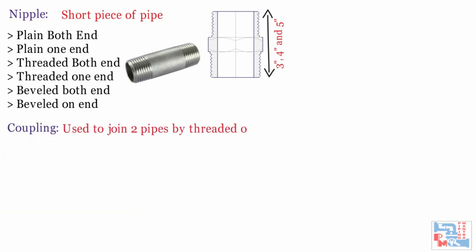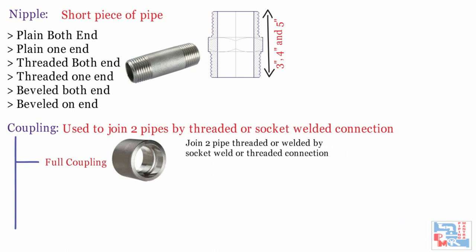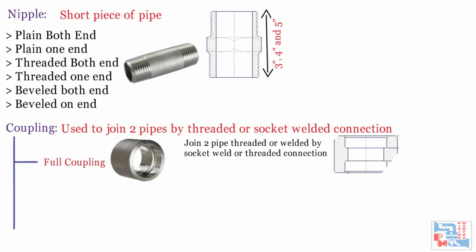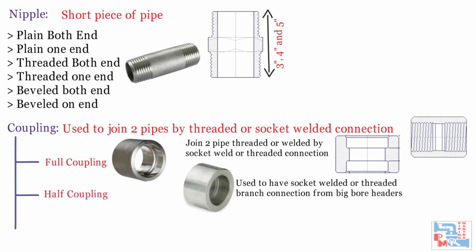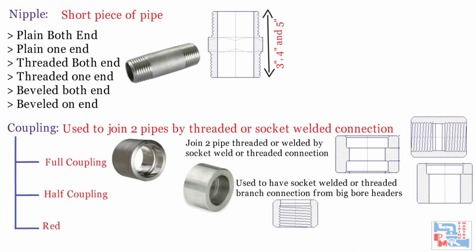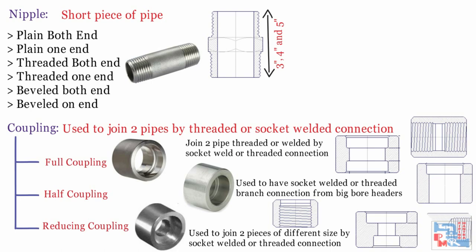Coupling is used to join two pipes by threaded or socket welded connection. Three types are used globally. Full coupling is used to join two threaded or welded pipes by threaded or socket welded connection. Half coupling is used to have socket welded or threaded branch connections from large-bore headers. Reducing coupling is used to join two pipes of different sizes by socket welded or threaded connection. After connecting, a coupling maintains the pipe centerline at the same elevation.